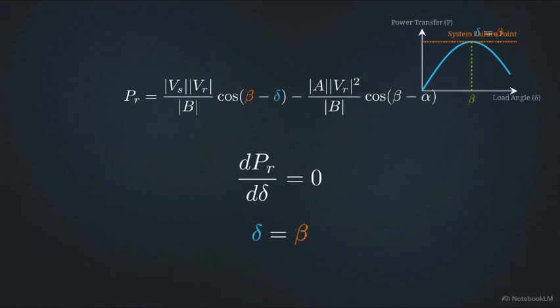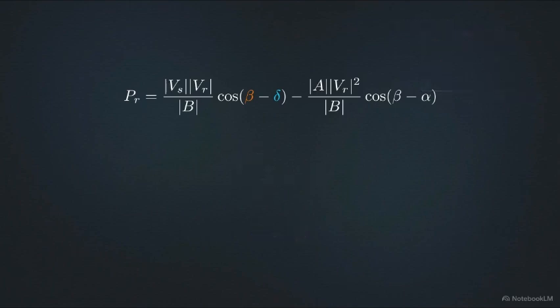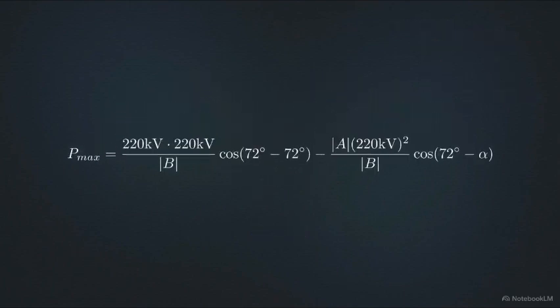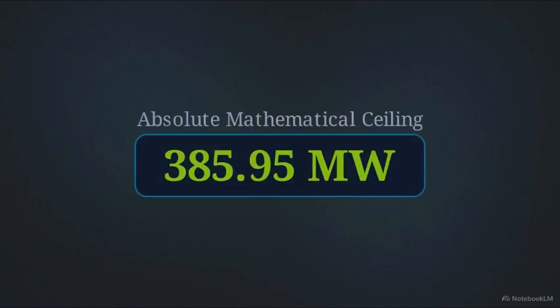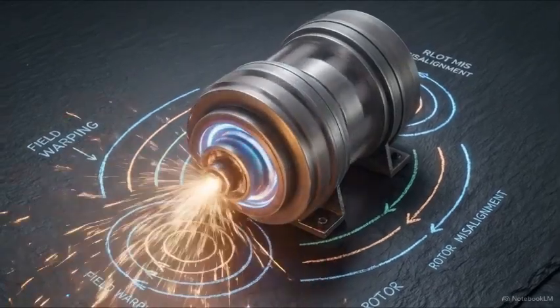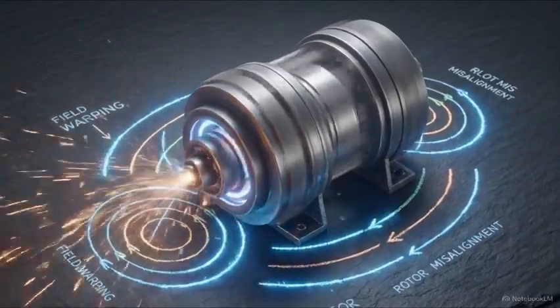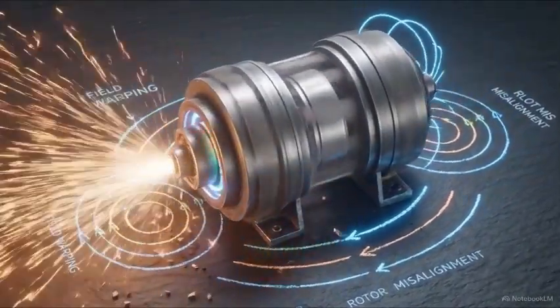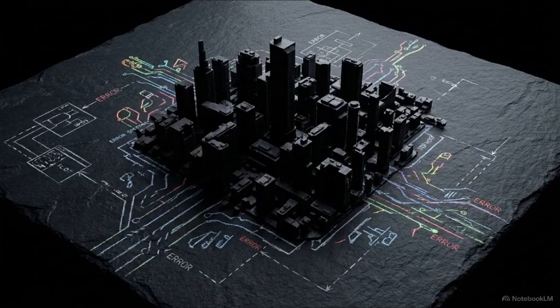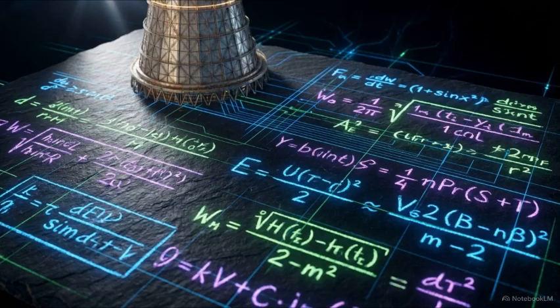On a 220 kilovolt system with a 72-degree impedance angle, matching the load angle to 72 degrees resolves to an absolute ceiling, exactly 385.95 megawatts. Pushing even a fraction of a megawatt past that resulting load angle breaks the physical resistance holding the system together. The generators lose their magnetic lock, the network loses synchronism, and the grid collapses. Preventing a blackout requires engineers to find mathematical techniques to bypass this rigid limit, rather than simply building larger power plants.